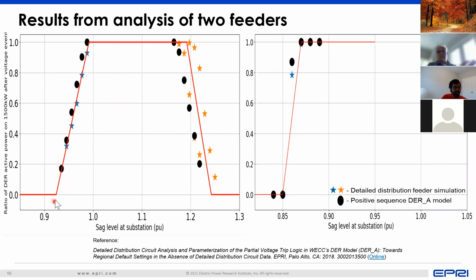So although the DER_A model has a linear characteristic, we see that depending upon how you parameterize it, you can get a representation of the amount of DER that trips, which is denoted by the black dots here, from the positive sequence domain, and they roughly lie within the characteristics that we obtained for the detailed feeder model. And this is for two sets of analysis of two feeders, wherein one had a more gradual drop-off, one had a more sharp drop-off, and we can really represent that characteristic.